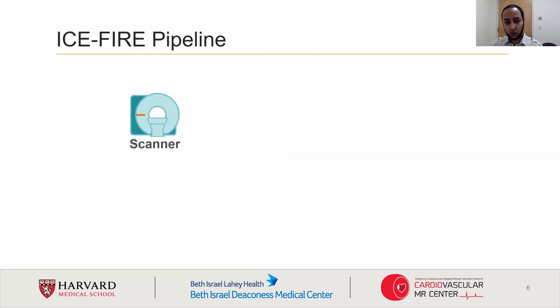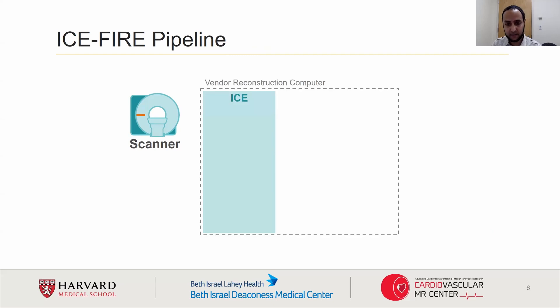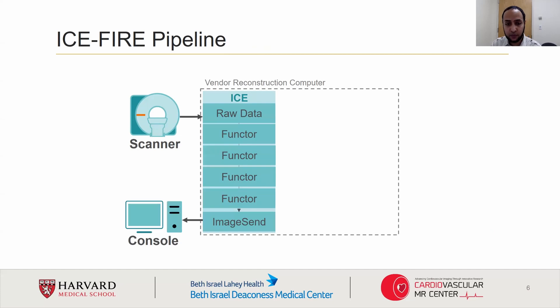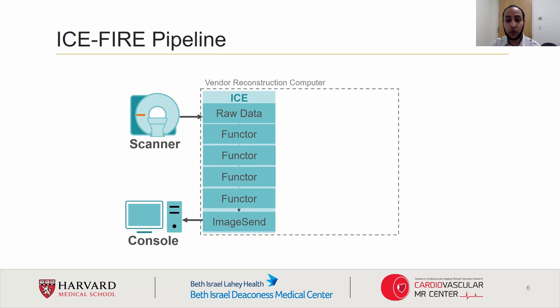Normally, when executing a sequence on the scanner, the reconstruction takes place inside of the image calculation environment called ICE. ICE is a server which is made up of various functors that process the k-space data and produce DICOMs, which are displayed on the console. However, it can be challenging for customers to program their own functors, and this limits the deployability of deep learning models.